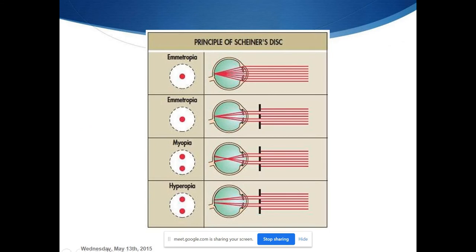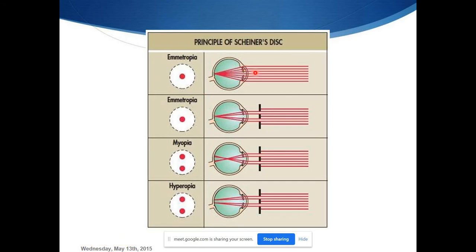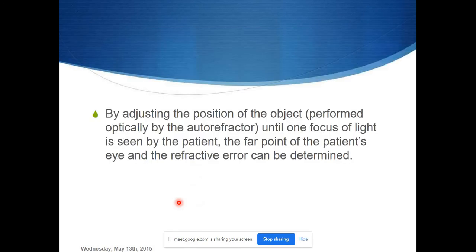This diagram gives a better explanation. In a normal emmetropic eye without a pinhole, a clear image is formed. With the double pinhole, both images pass through and form a single focused image. In a myopic patient, the two images separate and cross over. In a hyperopic patient, a different pattern is formed. This is the basic principle on which most existing autorefractometers work.